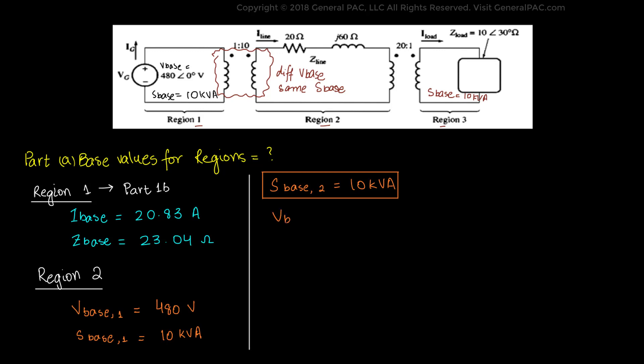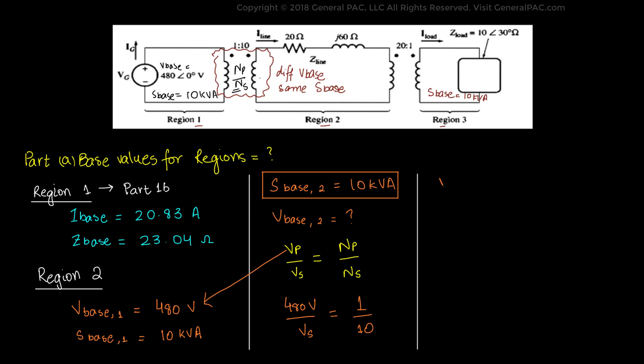Now let's find out the base voltage by using the transformer turns ratio. We can find the voltage on the secondary side using the equation: voltage on the primary side divided by voltage on the secondary side equals the number of primary turns divided by secondary turns. Since VP equals V1-base equals 480V, we have 480V divided by VS equals 1 divided by 10. Rearranging and solving for VS gives 4800V. So V2-base equals 4800V.